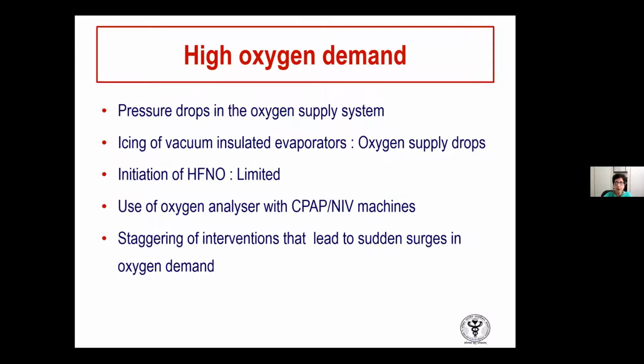One should also remember that if there is a sudden increase in oxygen requirement, there can be icing of the vacuum insulated evaporators or the liquid oxygen tanks, and the oxygen supply can drop because of that as well. One should ensure from the engineering teams that that is not the reason, but excessive use will obviously lead to pressure drops.